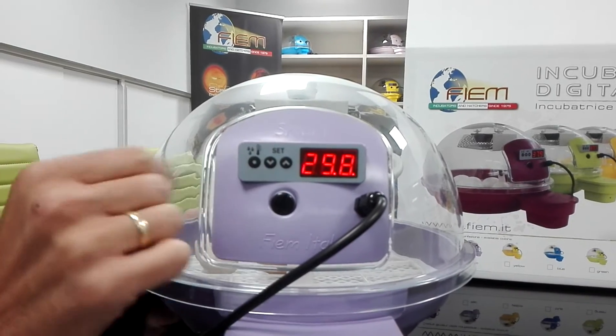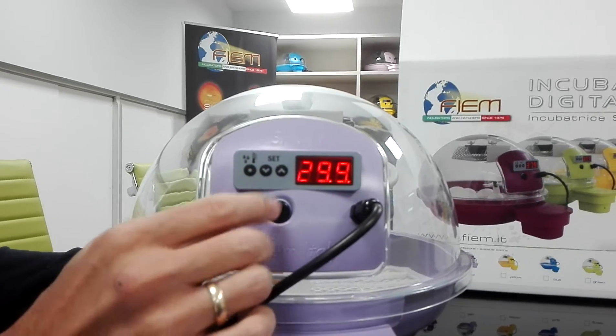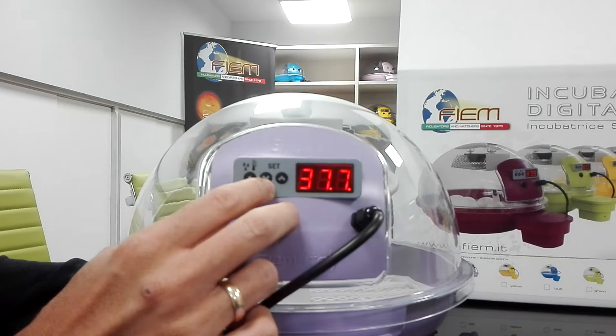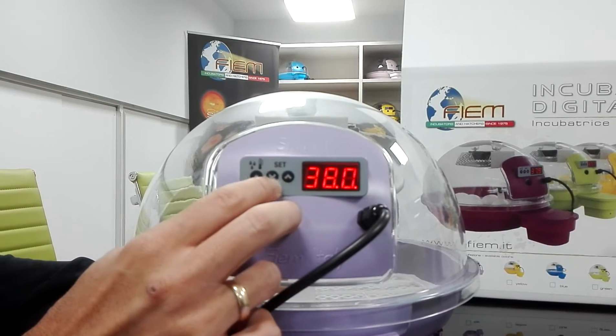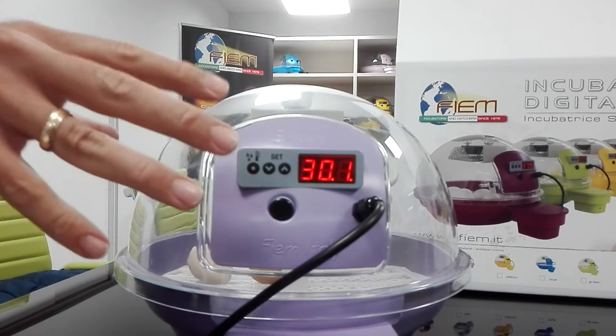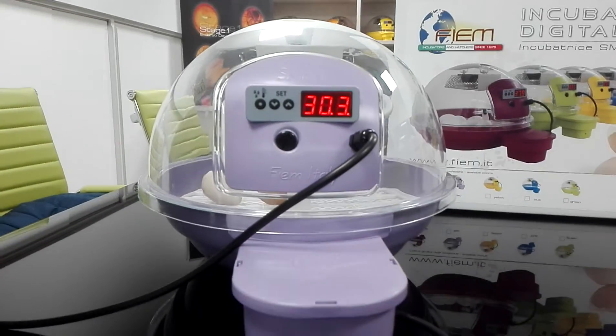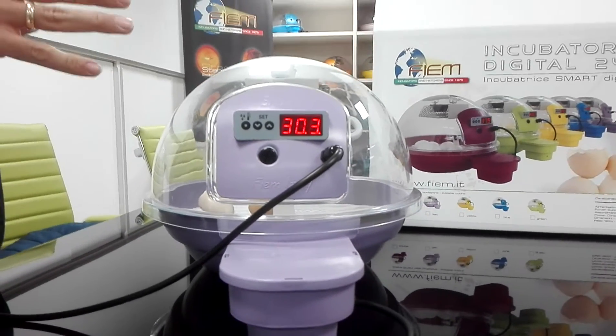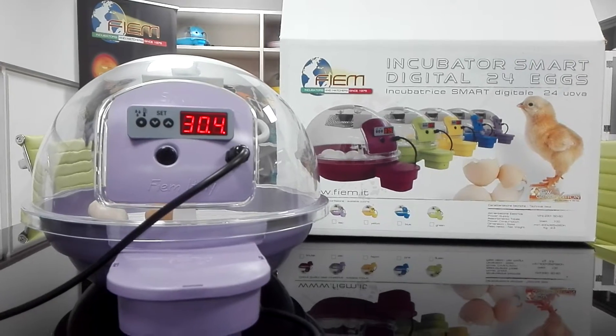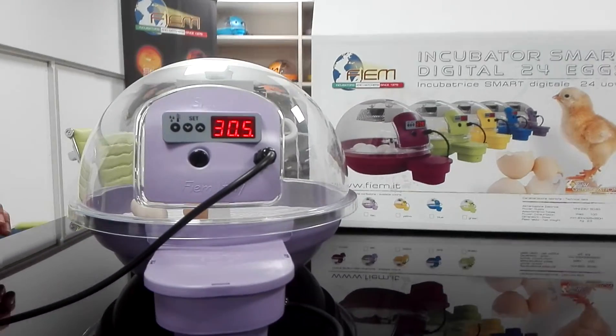It's very user-friendly and easy to understand. To adjust the temperature, you can act on the set keys — pushing them allows you to increase or decrease the temperature. The incubator is already set by the factory to the correct working temperature of 37.7 centigrade degrees, corresponding to 99.9 Fahrenheit degrees.